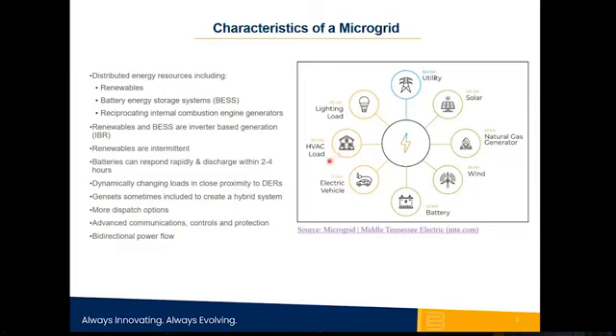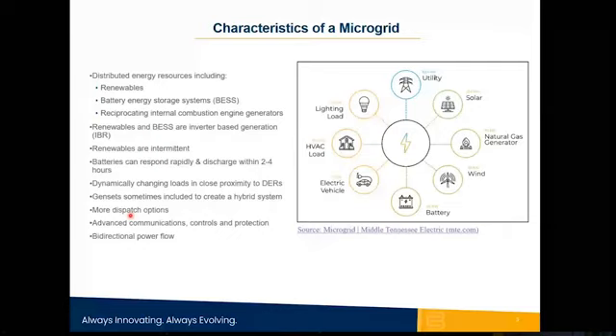When gensets are included in a microgrid, then it's oftentimes called a hybrid system. Sometimes you have a microgrid with strictly renewables and BESS systems. At other times, a genset is included, and that's a hybrid system. So that gives you more dispatch options. For instance, you can optimize the microgrid to dispatch to meet some higher order objective. For example, economics. If an aggregator or a developer wants to dispatch the microgrid to achieve the best economics, then he's going to give priority to those resources that are least costly.